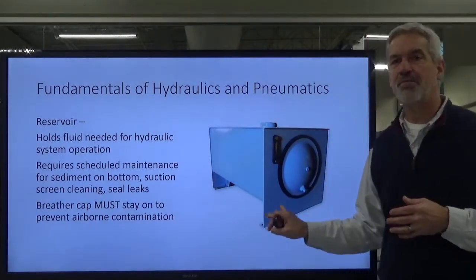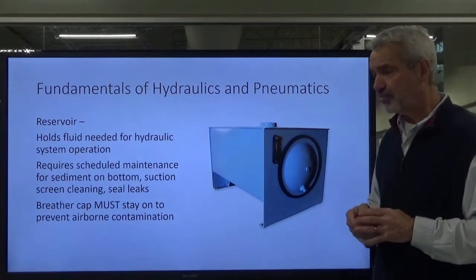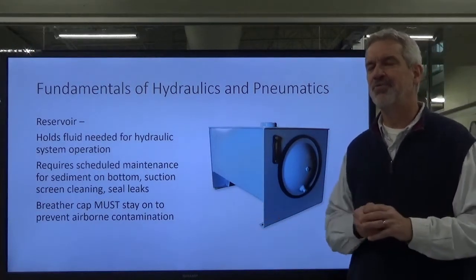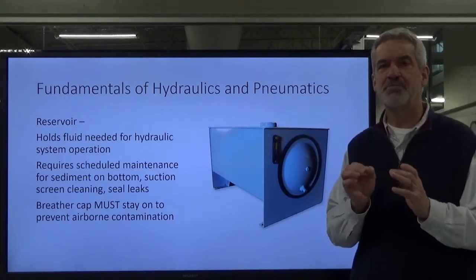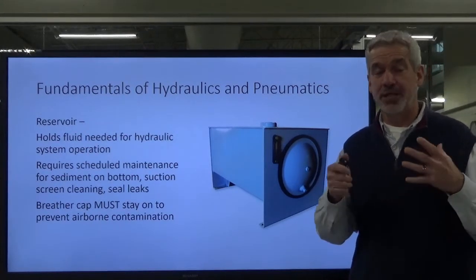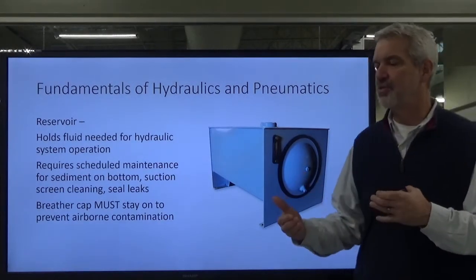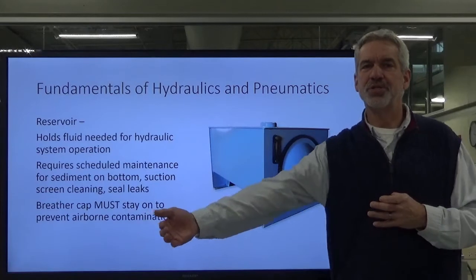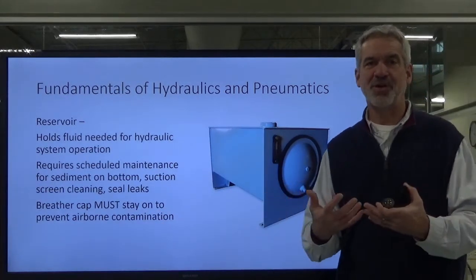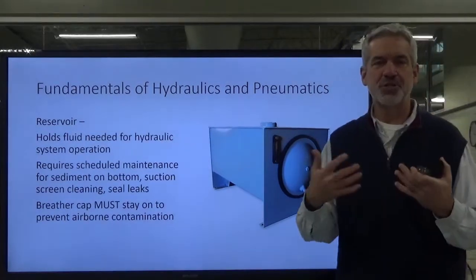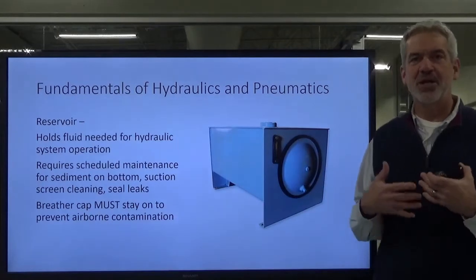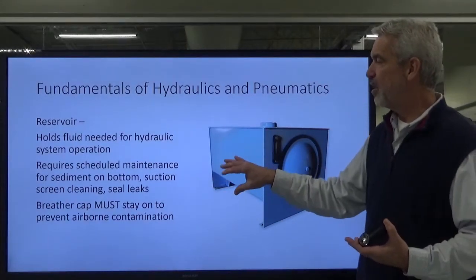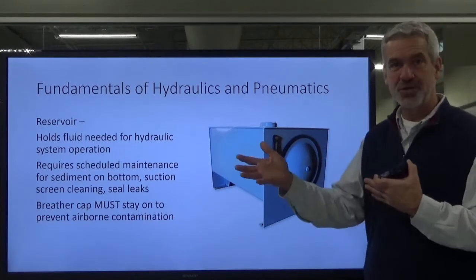A lot of people think it's just a vessel to hold oil, but no, there's maintenance that has to be done. It's critical because you'll get the oil flowing through your system. If you have the smallest leak, you'll rarely find a hydraulic system that doesn't have some type of very small, minute leak. But you want to keep those leaks to a minimum. If you've got a hose with a slight leak, when it strokes out a cylinder in one direction, it's pushing oil that way. On the return side, it's going to be drawing in probably atmospheric air and any dirt.